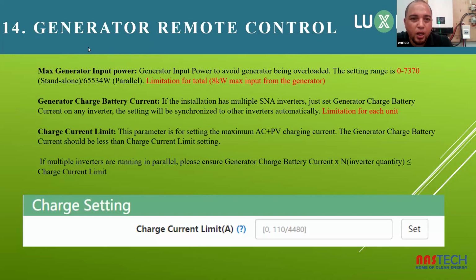For the generator remote control, the generator load input for the inverter is 8 kilowatt max. The inverter is mainly used to charge the battery. So you couple your generator to the inverter, and the inverter will use battery power to supply the load. And when the battery power is at a certain level, the inverter puts back the energy onto the battery for you to continue to use, to continue to supply the load.